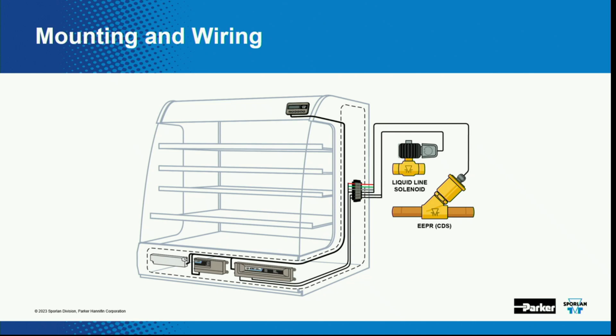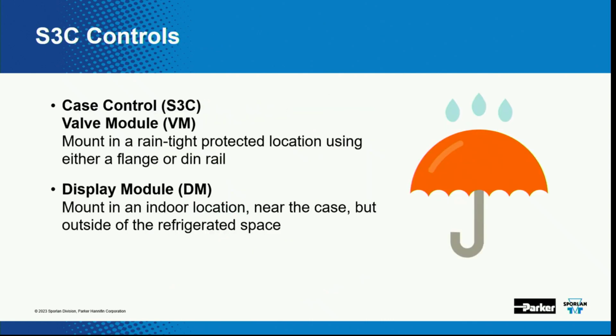This image here is just showing that somewhere on this case, you're going to have to figure out a place to put your controller - if you've got a valve module, a power supply, and the digital display. These are not always in the most convenient places. Wherever these go, you need to make sure they're underneath the umbrella because they're not IP rated. So if you hose them down, they are going to fry, most likely. They shouldn't be mounted inside of the refrigerated space - so outside of the refrigerated space.